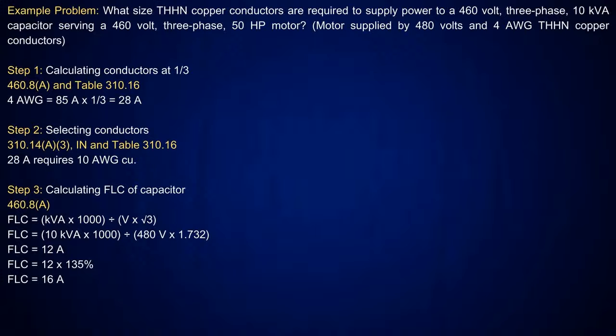Now, we're actually going to end up doing two calculations here. The first one is where we're calculating the conductors at a third. And the second portion is where we're calculating the full load current of the capacitor. So in this case, I was at 28 amps. I go over to Table 310.16. The next size above that is 30 amps, which is a number 10. Now, that's doing the conductors at a third.